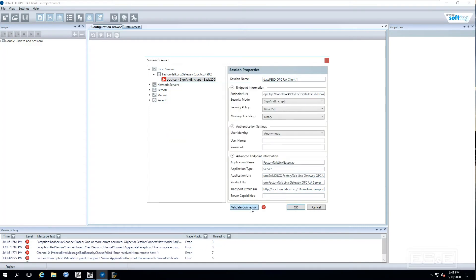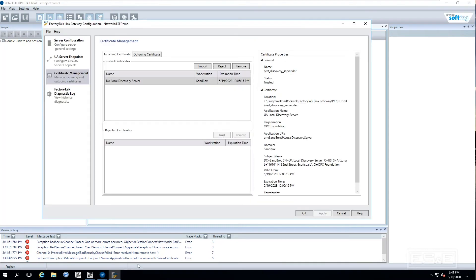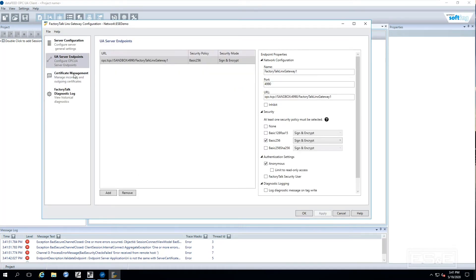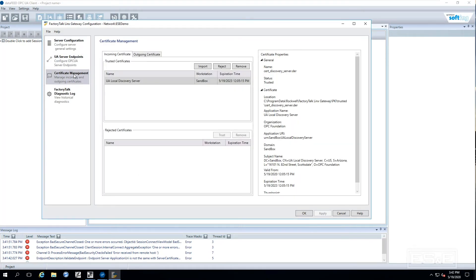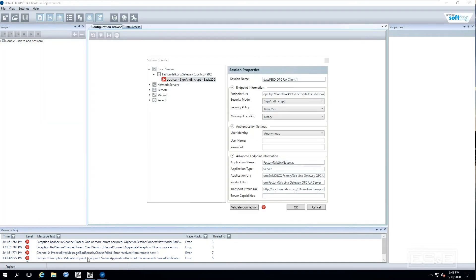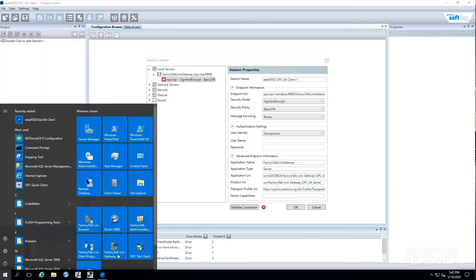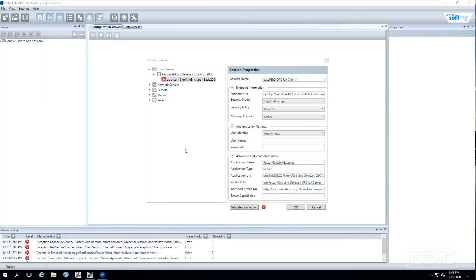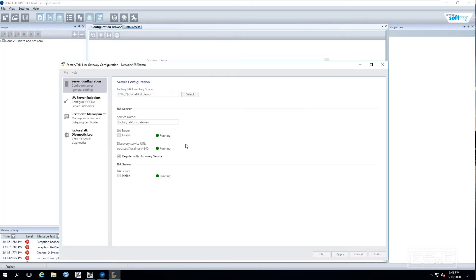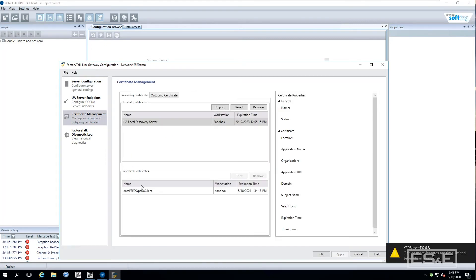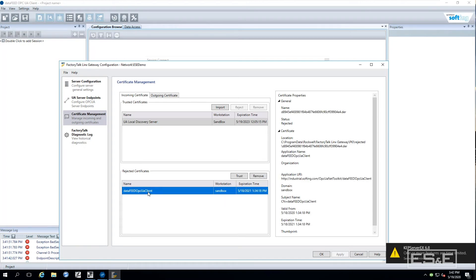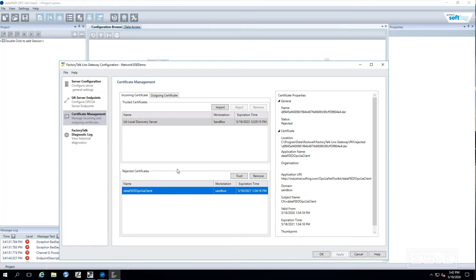My problem right now is because the factory talk gateway has got to trust the client. So sometimes you have to actually close the gateway application back down and restart it and go to the certificate management and you will see down at the bottom it is asking do we want to accept this because it is trying to register with us and we are going to say yep we are going to trust this OPC UA client.